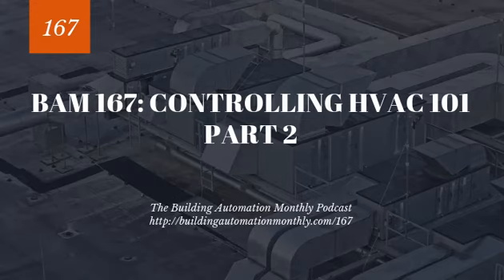I actually like it to be in a run that gives a good sample of a variety of boxes. So if you have an intermix of cooling only and heating boxes, then I like to have the 2/3 sensor, quote unquote, the discharge air pressure sensor.